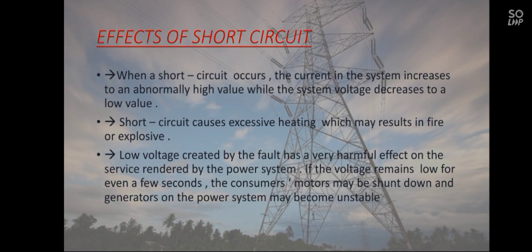When a short circuit occurs, the current in the system increases to an abnormally high value while the voltage decreases to a low value. Short circuit causes excessive heating which may result in fire or explosion. Low voltage created by the fault has a very harmful effect on the service rendered by the power system. If the voltage remains low for even a few seconds, the consumer's motors may be shut down and generators on the power system may become unstable.